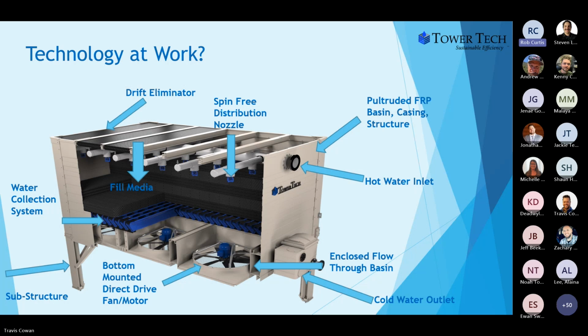The third thing is the variable flow capability. Cooling towers have been on-off pieces of equipment for years, and what happens is if you reduce flow across the distribution system in cooling towers, you lose your pattern, which means you're not covering the fill material effectively, which means you have a reduction in performance, and you also have increased maintenance that can happen because you're getting wet and dry with your media. TowerTech's development of that spin-free distribution has variable flow capability from a 3-to-1 turn-down ratio, still covering 100% of the surface area, has tremendous impact on energy, on maintenance, on the safety, and even the longevity of the distribution system and the whole cooling tower.